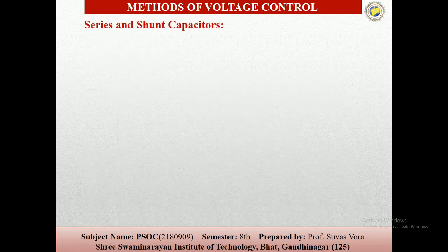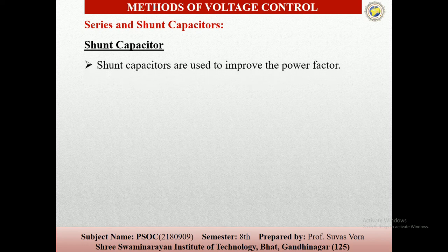Now the last method of the voltage control system is the series and shunt capacitors. So now we can talk about the shunt capacitors. The shunt capacitors are used to improve the power factor. They supply the proper amount of reactive power to maintain the proper voltage. The capacitors are mainly connected to the bus bar and placed along the transmission lines to limit the load and the voltage drops.